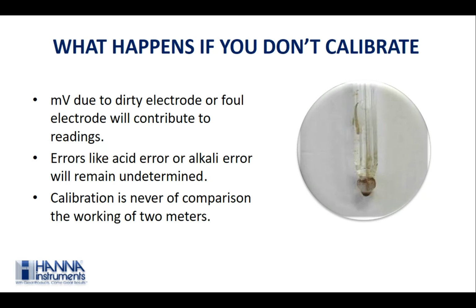The most important thing each and every user should take into consideration is that calibration is never done for the comparison of two different meters. Although all the instruments are tested with similar standards, each and every electrode is different and the response is also different.